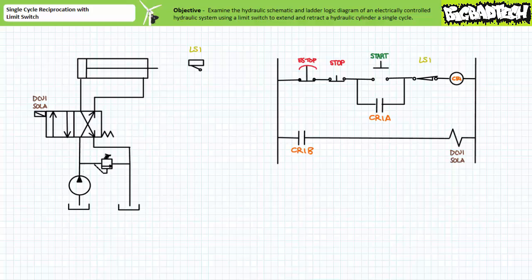Valve position is the property that controls actuator direction, and the electrical aspect of this system controls valve position. On the hydraulic and mechanical side, a jammed spool, jammed cylinder, blocked port, or simply not turning on the pump could also cause this same problem — however you would be able to observe both the relay and solenoid function. Very often it is desirable to isolate primary hydraulic and pilot electrical circuits from one another for independent test and troubleshooting purposes.